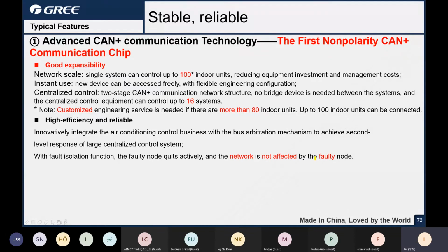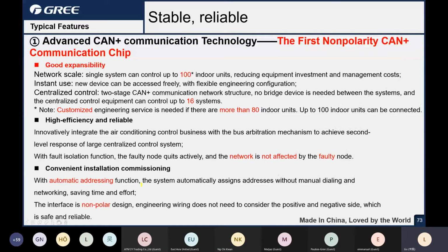That means the units can keep communication and keep run. A lot of advantage is the addressing. That's automatic addressing for the CAN Plus. No need to do dip switch or setting or anything. You just press the button to net the units, distribute the address by itself, and the interface is non-polarity. You can do the opposite match or cross match. Okay, you can just connect the cables as you wish, as you like. No polarity. Okay.